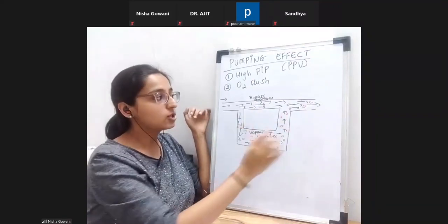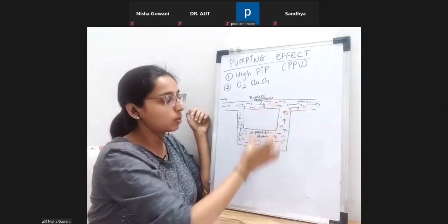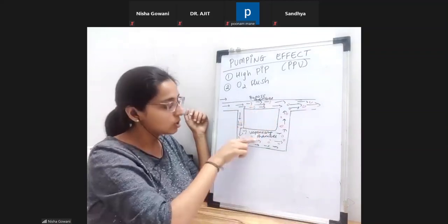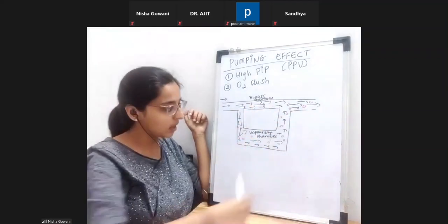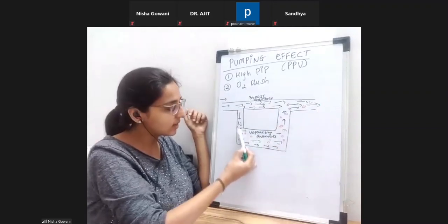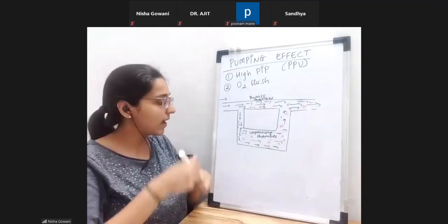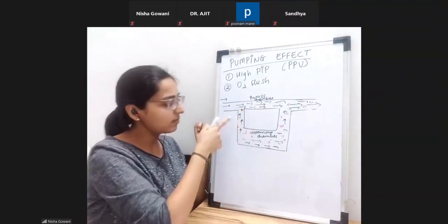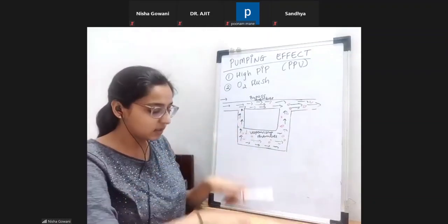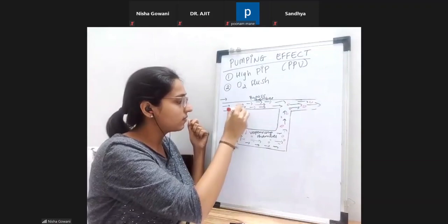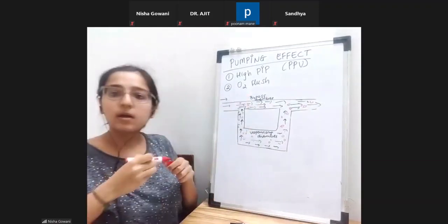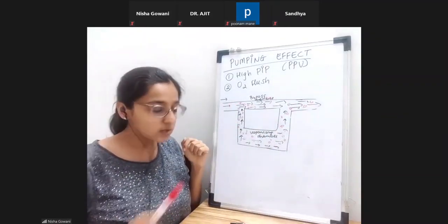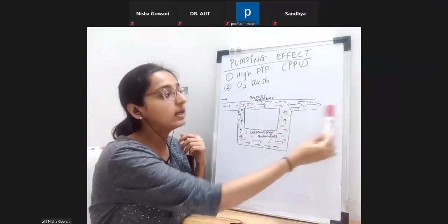Initially, this was the only area with the low pressure, and these both were high. So high to low pressure was going very fast. During that phase, now the pressure here dropped. So this is already going in this direction, but now this will start flowing in reverse direction also. So at one point, there will be reverse movement. Do I have a valve over here? No, I have nothing to protect against this reverse movement. So now these vapors along with the gas will go in reverse direction. They will start moving in reverse and go via the bypass chamber. This will cause a very high amount of vapors getting delivered to the patient.